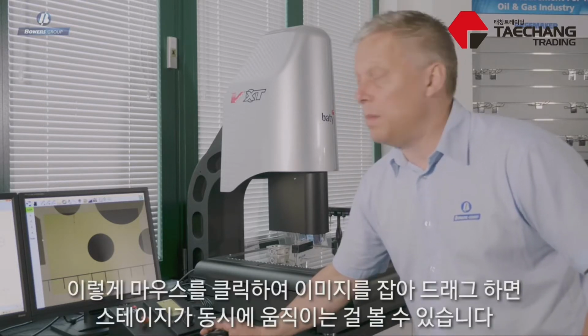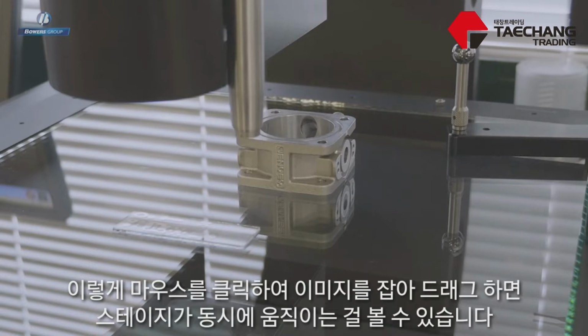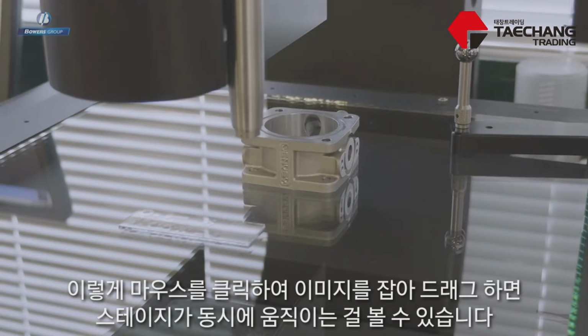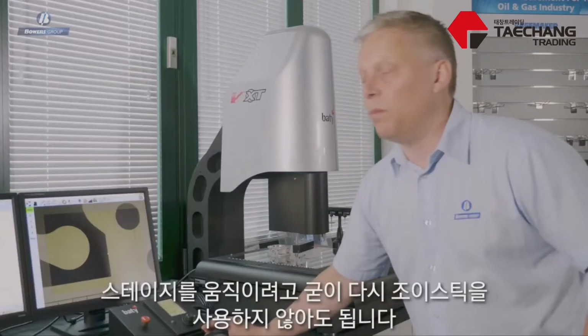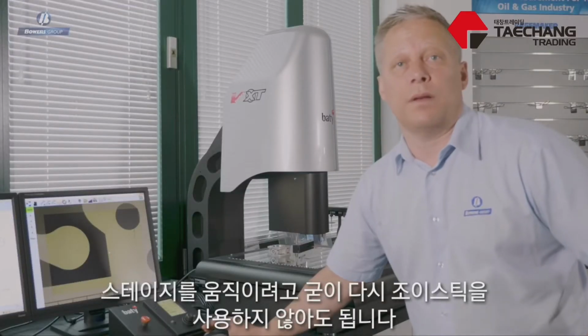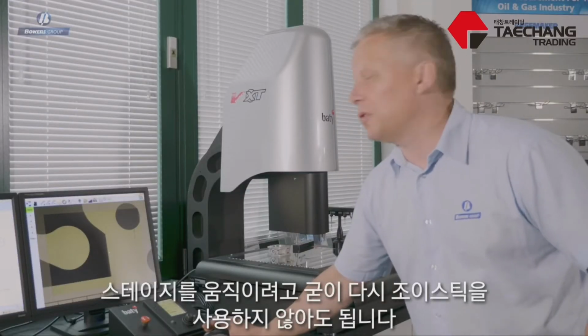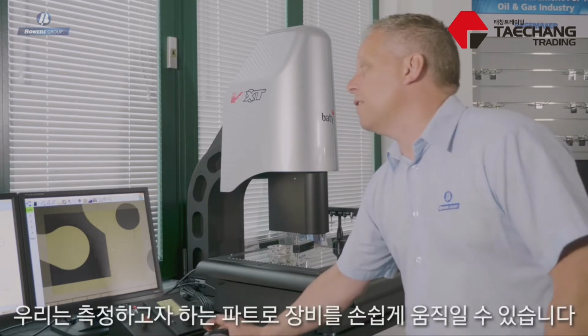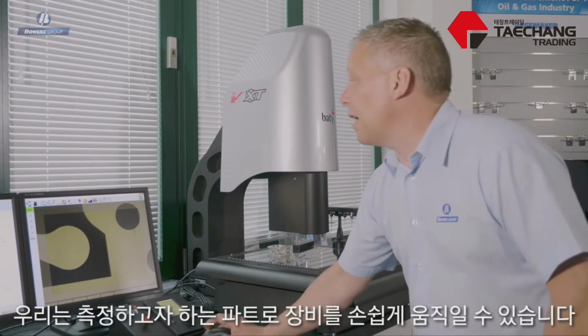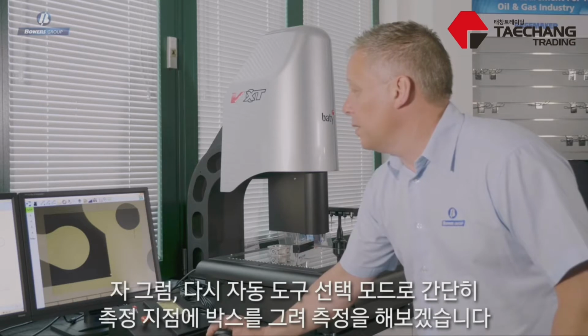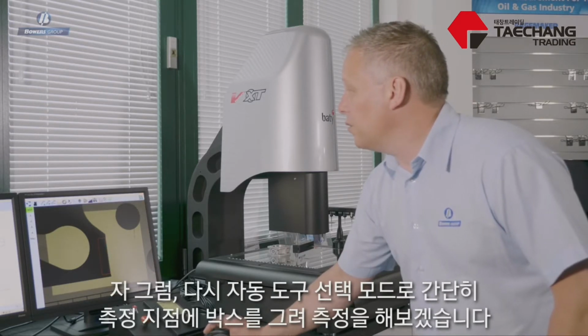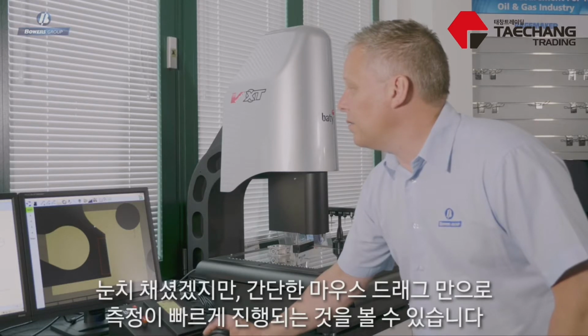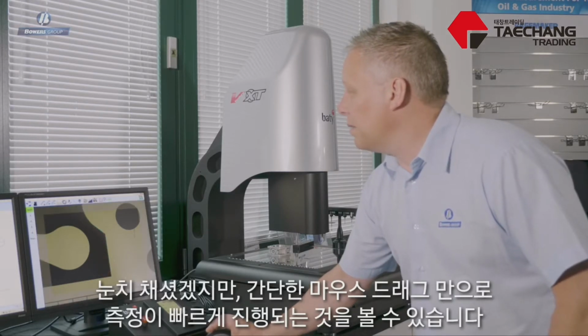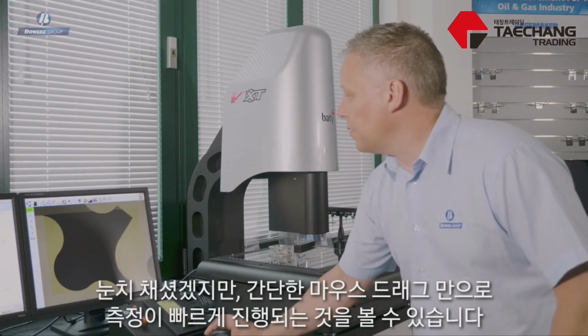Okay, so a great tool that we have on the Venture XT is the ability to drive the stage using the mouse. If I just click my mouse and grab the image and drag it across there, you can see that the stage does a corresponding move. I don't have to take my hand from the mouse onto the joystick to do that, and that's a really convenient way of driving the machine around the part that you want to measure. So again, using the auto select tool, I'm simply drawing boxes, and you'll notice this time I'm speeding things up using the mouse drag tool.